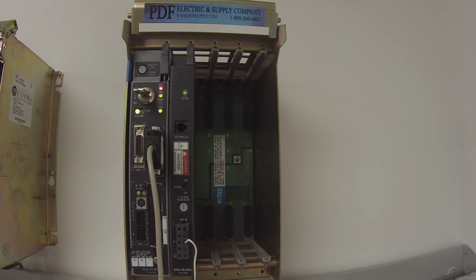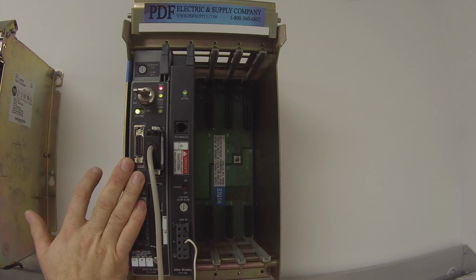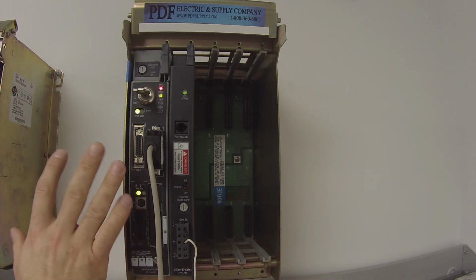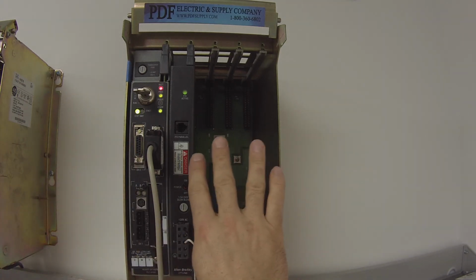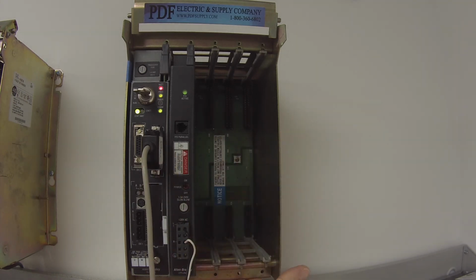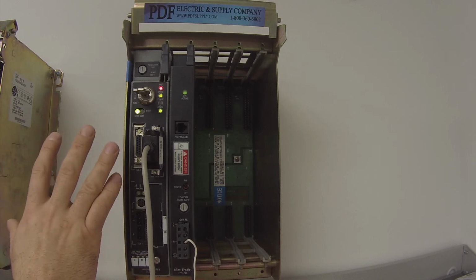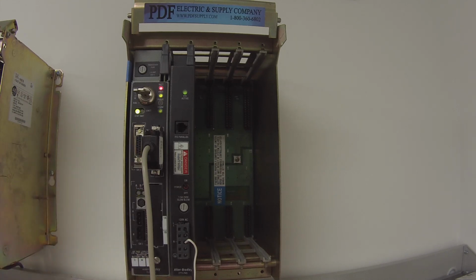Make sure that it can go into run mode. Another thing that you would want to do is to leave this processor in run mode for a day, a couple days, maybe over a weekend, 2 or 3 days. And what you want to do is try to see if you can make it kick itself out of run mode. Perhaps put I/O modules to the right to fill up the rack. You can cover the bottom with plastic, the top with plastic, so that heat has difficulty escaping, and it puts the processor under a little bit more strain, just to test its durability.